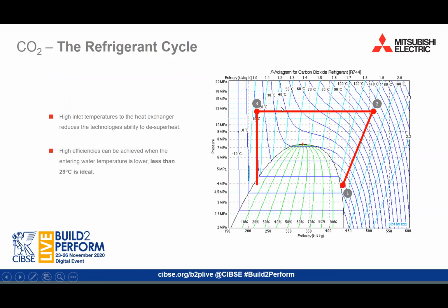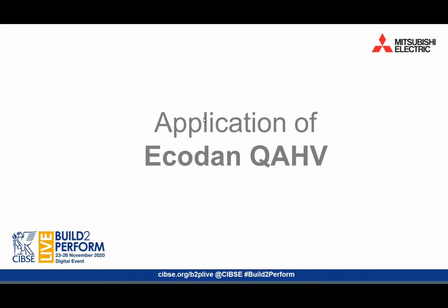At point 3 again, the refrigerant enters into the expansion valve where the pressure and temperature are both reduced before entering into the evaporator at point 4. This cycle is the unique feature of CO2 heat pumps and is the reason why such high temperatures can be achieved with large delta T's and with such high efficiencies. So now, having introduced the technology, let's take a deeper look at how we can design the system to make the most of these features. So the next few slides introduce some potential hydraulic arrangements and the basic control requirements.